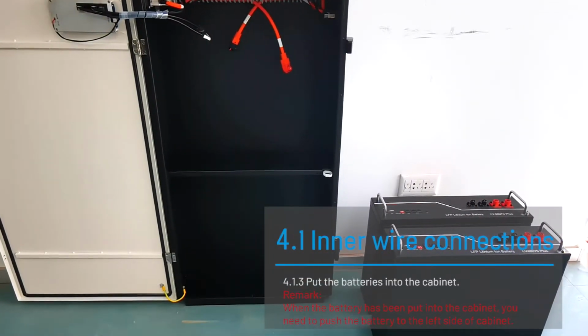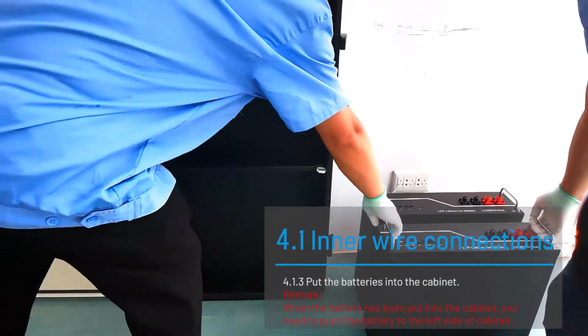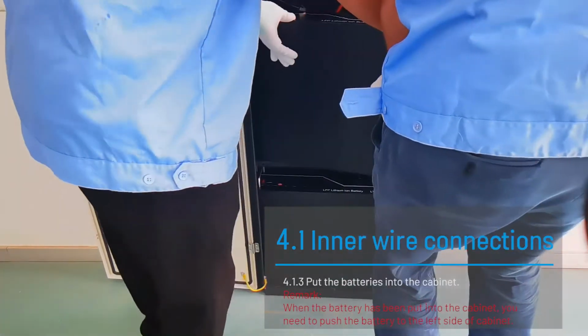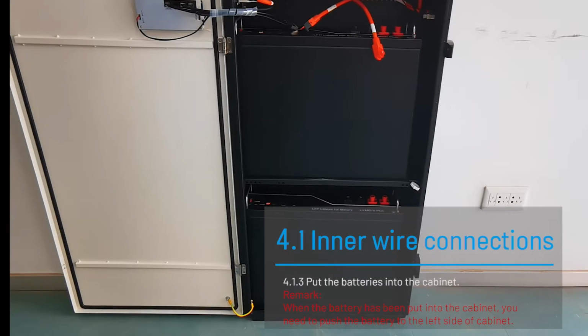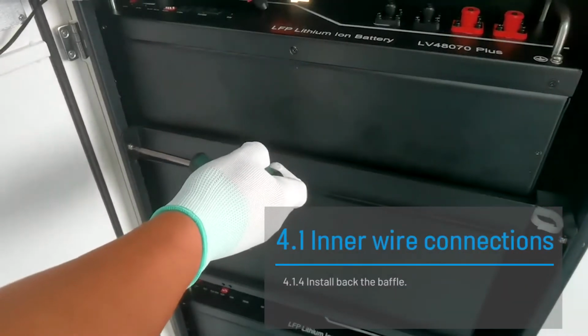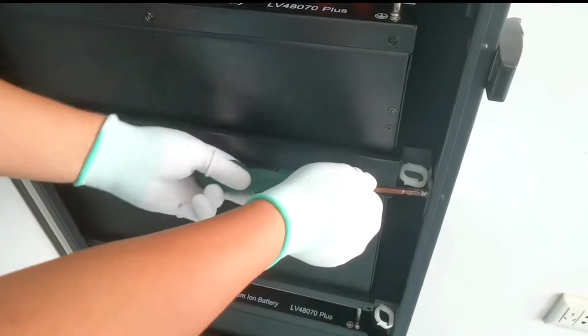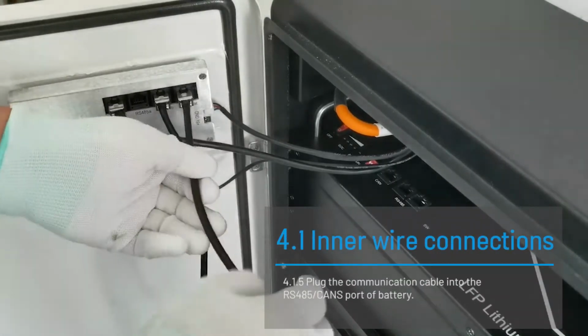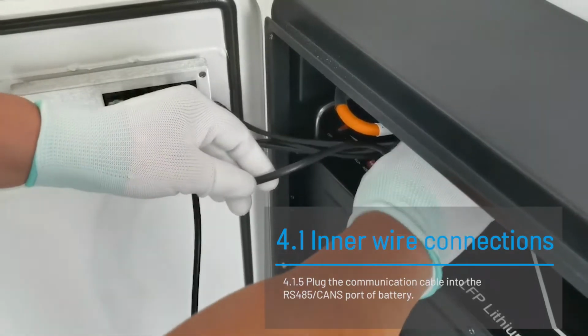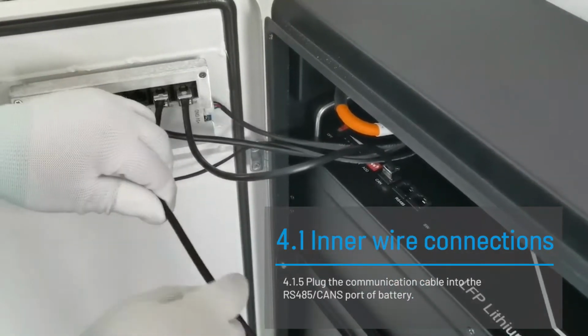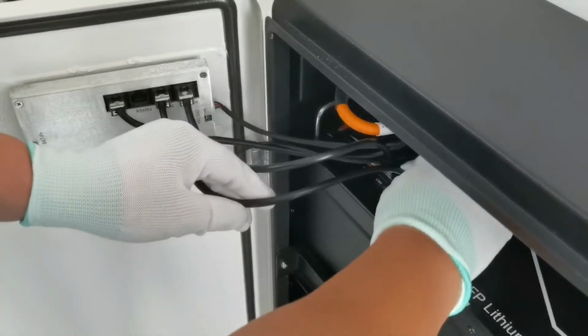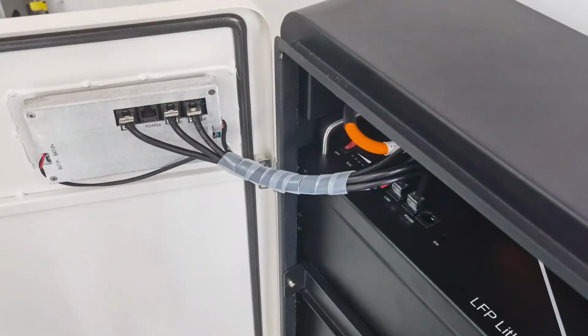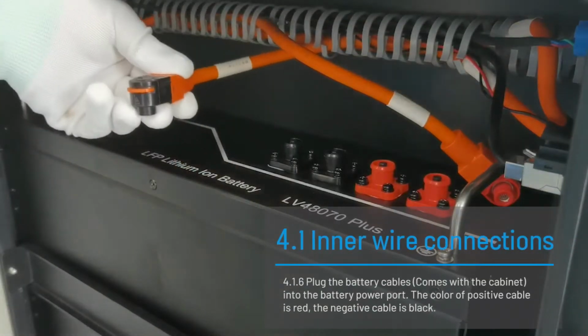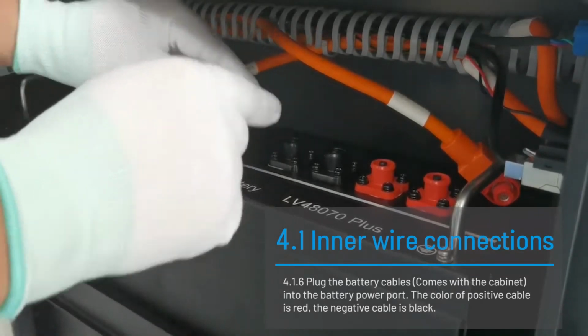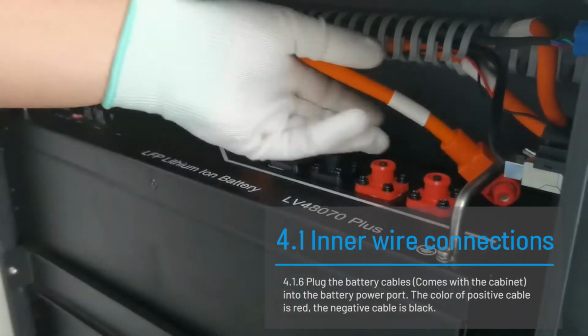Put the batteries into the cabinet. Remark: when the battery has been put into the cabinet, you need to push the battery to the left side of the cabinet. Install back the baffle. Plug the communication cable into the RS485/CAN port of the battery. Plug the battery cables into the battery power port. The positive cable is red, while the negative cable is black.